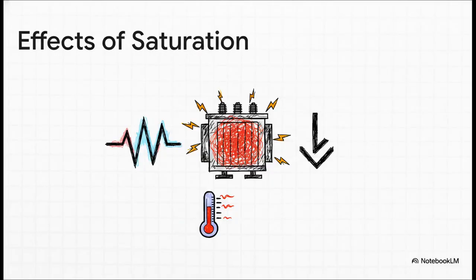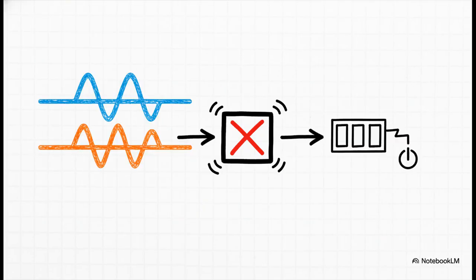And this saturation has three really nasty consequences for the grid. First, you get harmful even-order harmonics. They can cause protection systems to misoperate, tripping key assets offline.